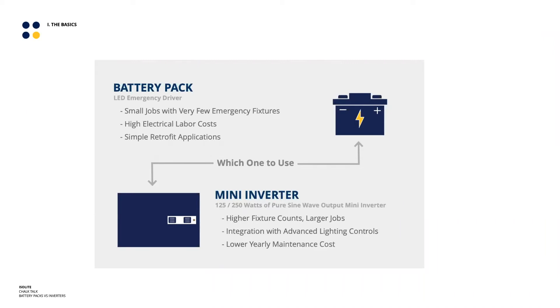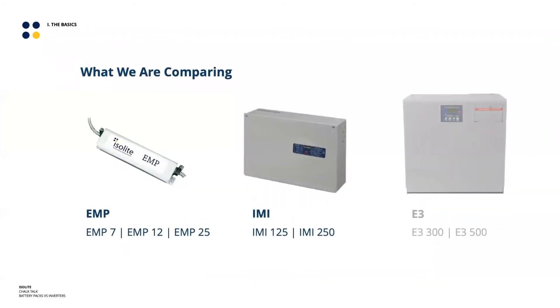The inverter has an advantage when you get into higher fixture counts — really after fixture five, six, seven, and up. If you're trying to integrate with advanced lighting controls like zero-to-ten volt, DALI, or phase control, you'll want to be in inverter territory. And if your goal is to reduce yearly maintenance cost to the maximum extent, that's where the inverter wins. These are the general criteria to pick between the two.